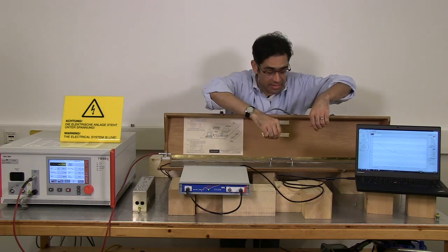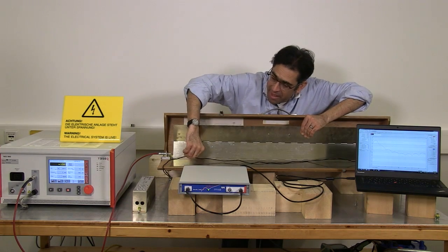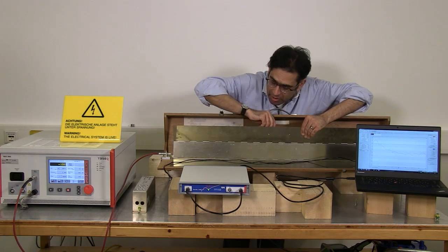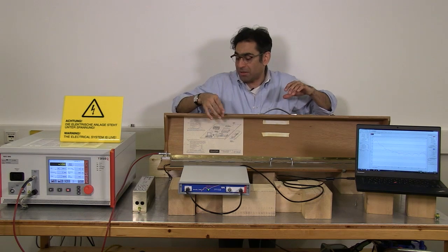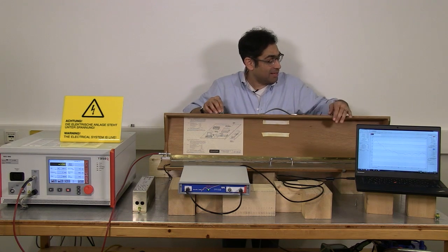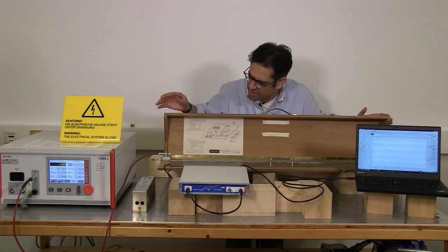And these are all defined in the standard. And they need to be coupled somehow to the cables. Here I have got a capacitive coupling clamp. And as you can see, we have passed the power cable of our Bode 100 down here. Please note that these tests are delivering enough energy to be harmful. So you have to be very careful when you're doing this sort of test.